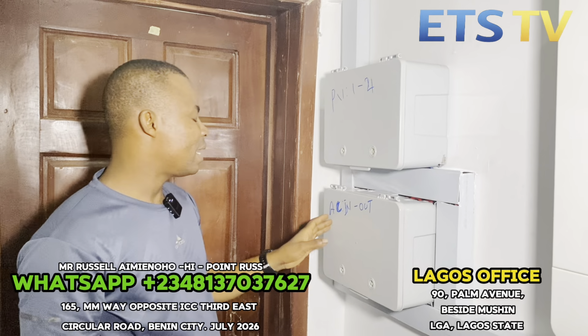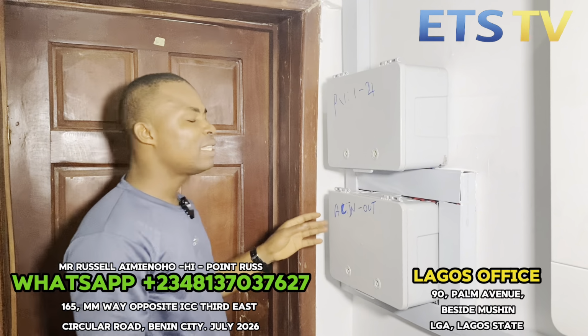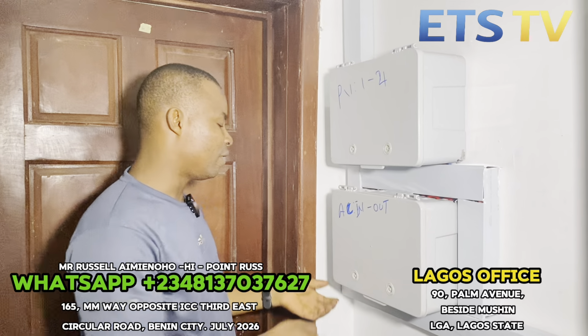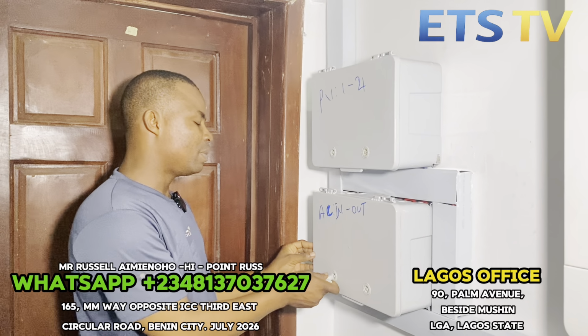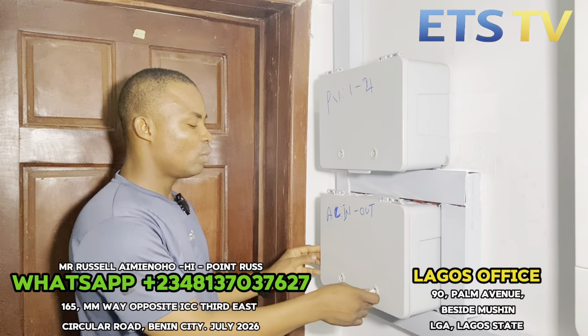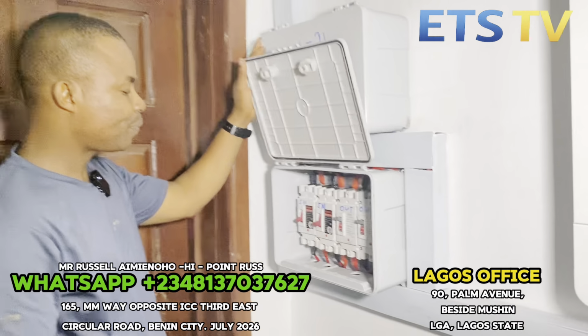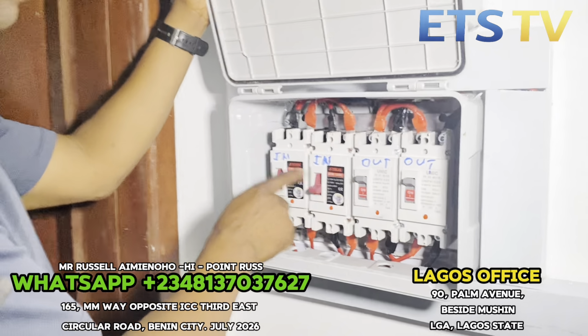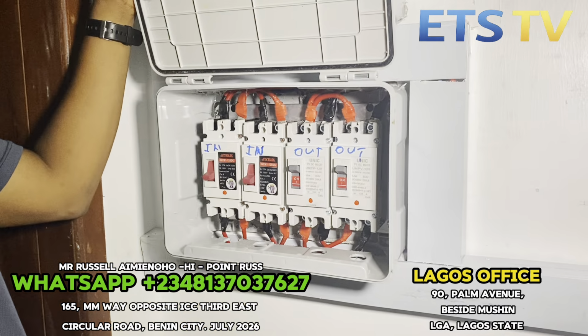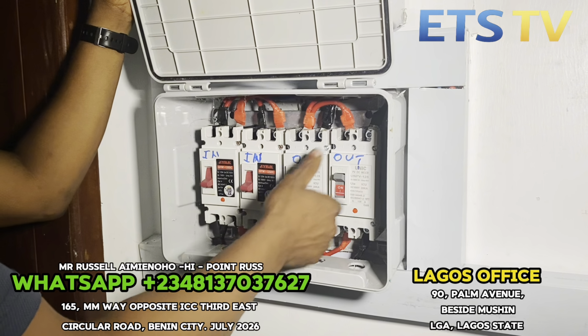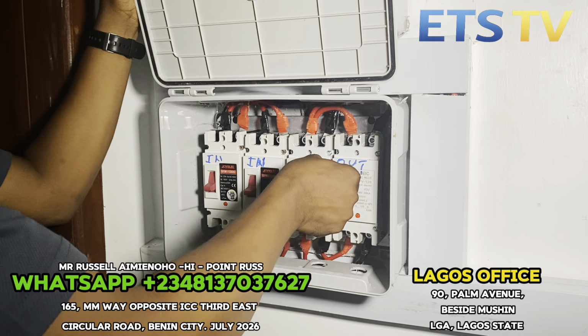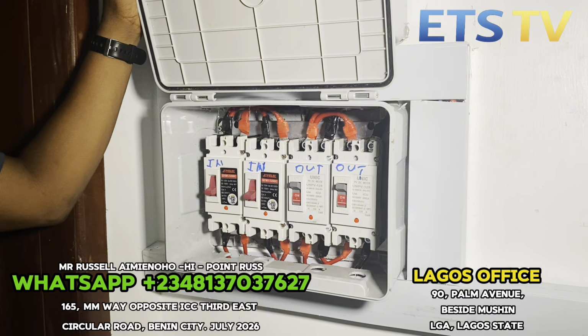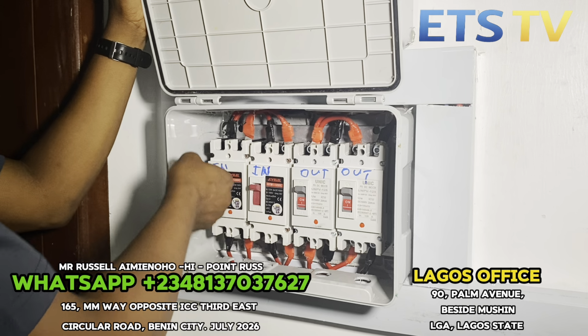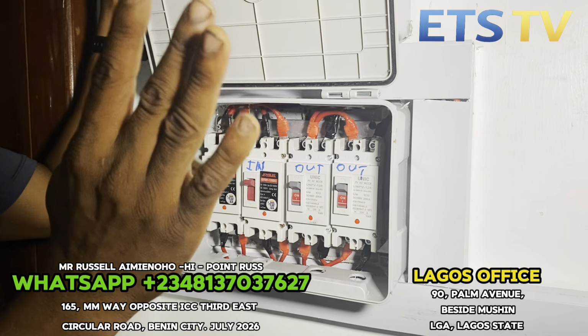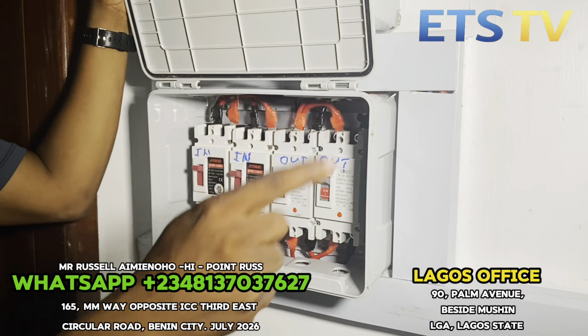Down here we have the AC in and AC out. AC in means grid or generator, which is NEPA. The out means load to the house. For the in, we offer this because NEPA light isn't actually available for now, while the out goes to inverter 1 and inverter 2, and then to the house load. So when NEPA brings light, it supplies NEPA, and when NEPA takes the light, it supplies from the inverter.